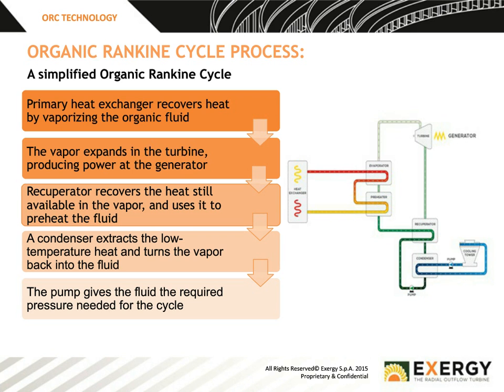This helps recover a little bit more energy from the heat of that fluid, and is used to later preheat it. Then it passes through a condenser, which turns the vapor back into a liquid. That condenser can be either liquid-cooled or air-cooled, depending on the environment. Finally, a pump, which just gives pressure to the cycle. And then we have this liquid circulating again.